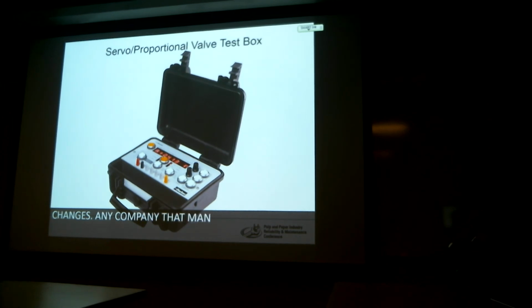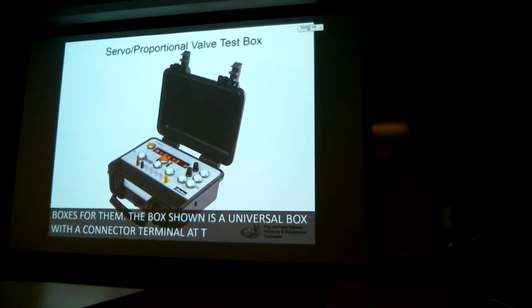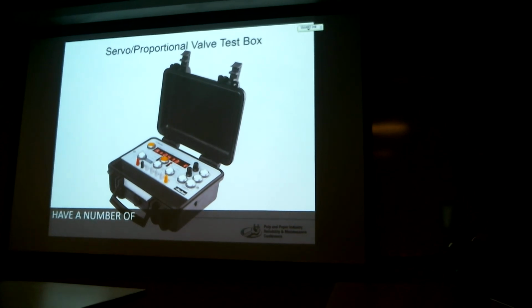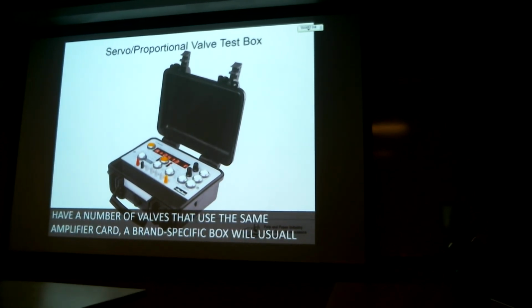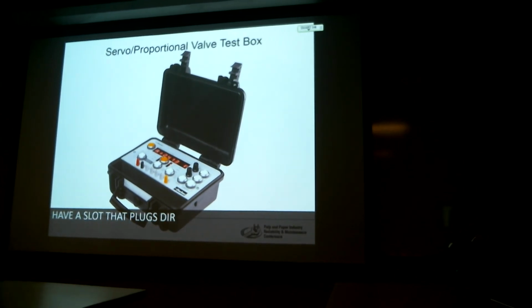Any company that manufactures servo or proportional valves will also make test boxes for them. The box shown is a universal box with a connector terminal at the front. If you have a number of valves that use the same amplifier card, a brand-specific box will usually have a slot that plugs directly to the card.